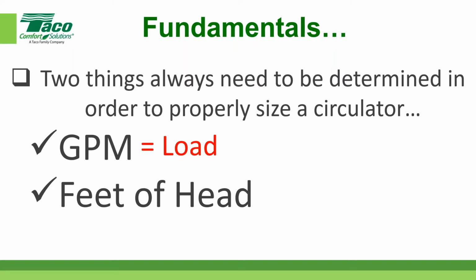Oftentimes those, and should be in a lot of cases, depending on what you're using to build the system, but all day long people have used 30-degree delta T's for panel rads. And a lot of that is driven by the way they're piped up. Are we using small tubing to get out, and doing home run systems, kind of like Siegenthaler has shown, for zoning back at the manifold? The smaller pipe is not going to allow you to do real tight delta T's.